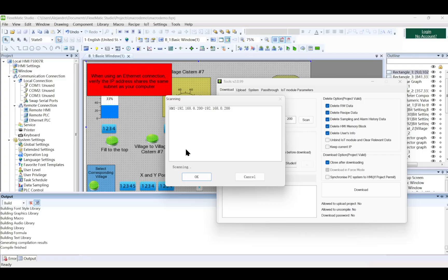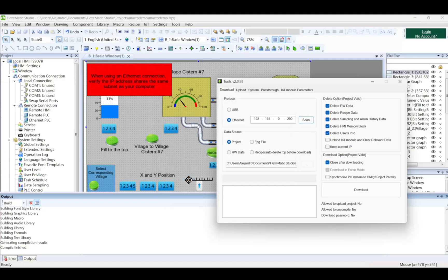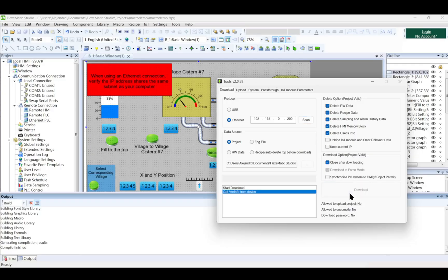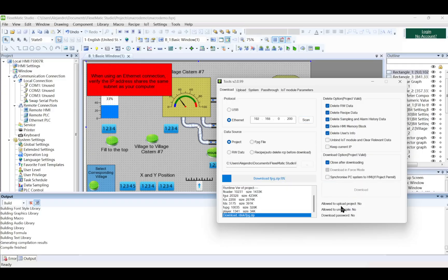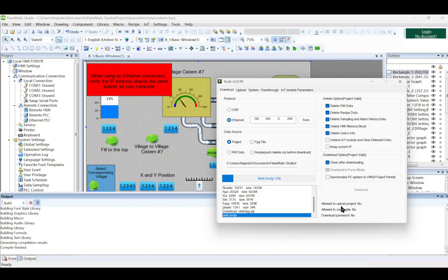Troubleshooting Common Errors. If the error message Communication Failed appears, verify that the download cable, USB or Ethernet, is properly connected. If the error message Failed to start the slave computer appears, power off the HMI, restart it and try again.